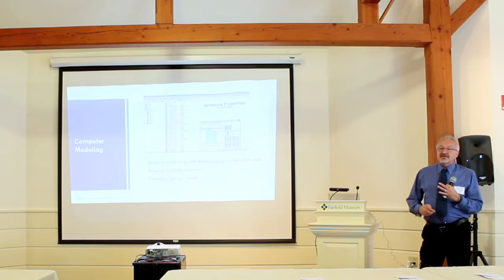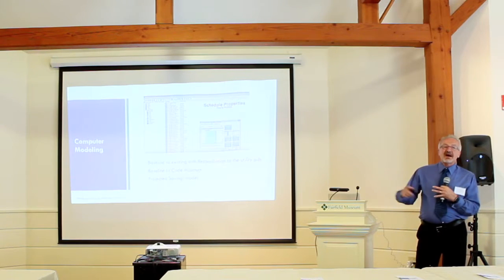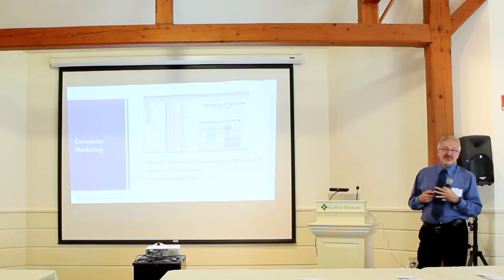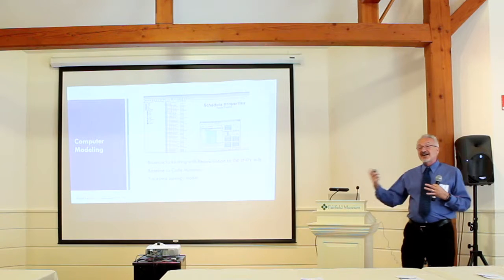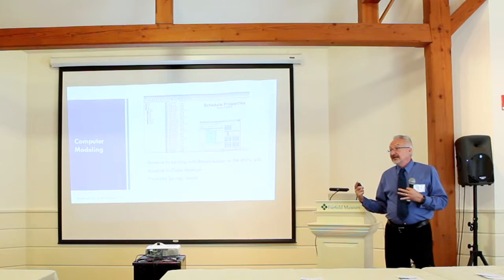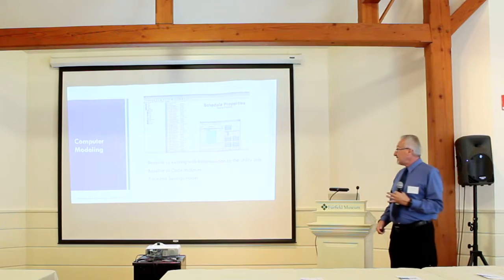A lot of the utility companies don't care where your building is right now when they're giving your incentives based on this. They want to know where code minimum is. So what we have to do is go through and we would model your building as it is, reconciling. Then we have to do another model as if your building met the current codes, whatever the current codes are, or whatever code they recognize. And whether it's the utility company or CPACE, or whether it's the IRS, because some of your incentives are based on this modeling, they have a different baseline. So we have to make sure that we're using the right baseline and the right code for that baseline.